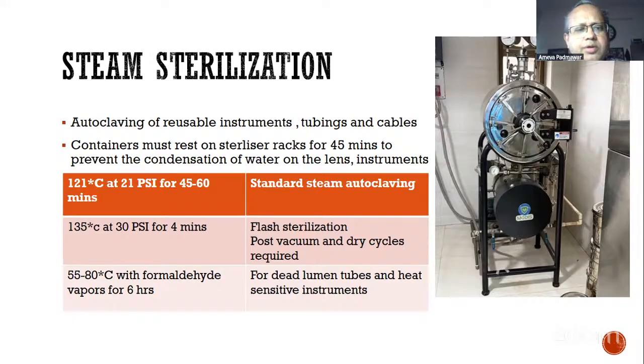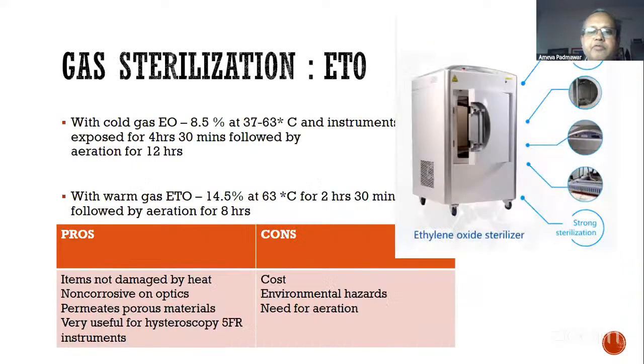Then there's one more way of steam sterilization which uses formaldehyde vapors at 55 to 80 degrees Celsius, and this exposure is for 6 hours. Not recommended, because formaldehyde is harmful to the health of the healthcare professionals and is carcinogenic. But it is very useful for tubular structures. It cleans the inside of these tubes as well, and especially those which cannot be heated up. It is a modality, but I do not recommend that for any of it.